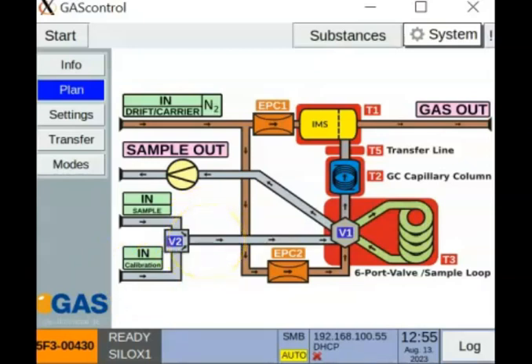The gas will be aspired by the sample pump through the sample loop, and we have a 6-port valve, valve 1 here, which switches from filling the loop to the injection position, where we will have the sample transferred onto the GC column, and after separation the analytes will enter the ionization chamber of the ion mobility spectrometer and produce the signals of the analytes.